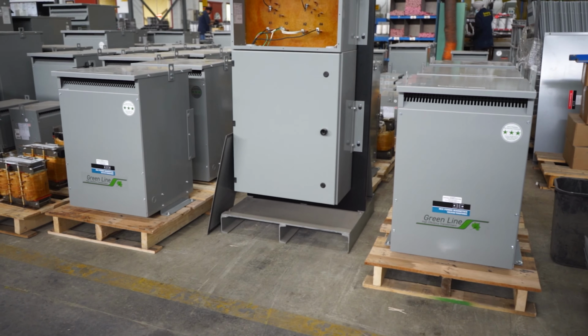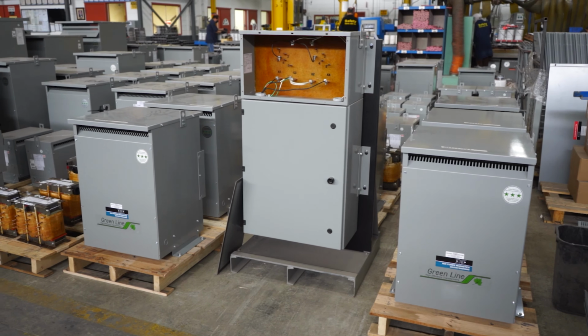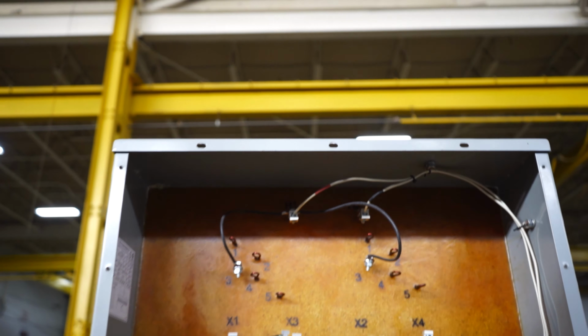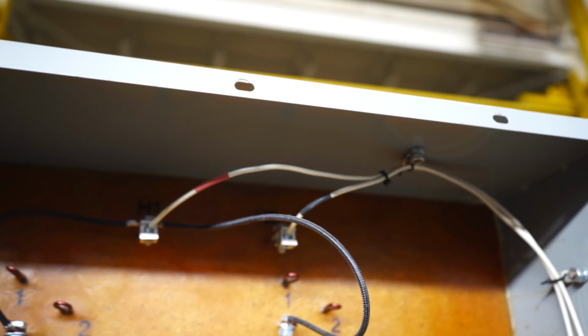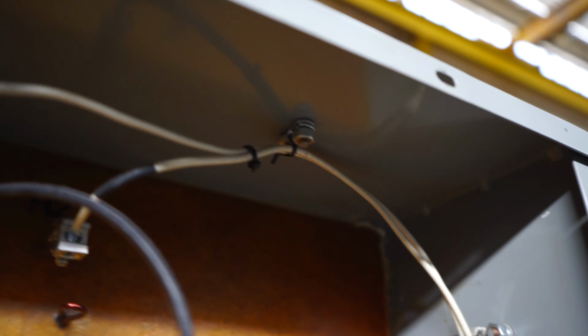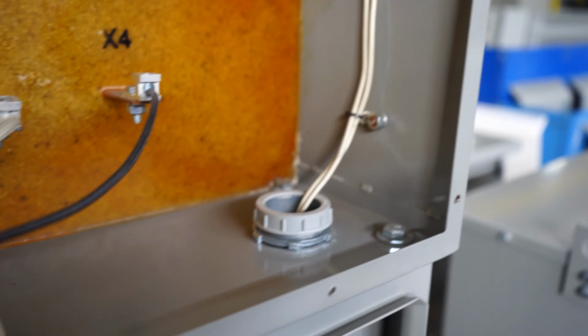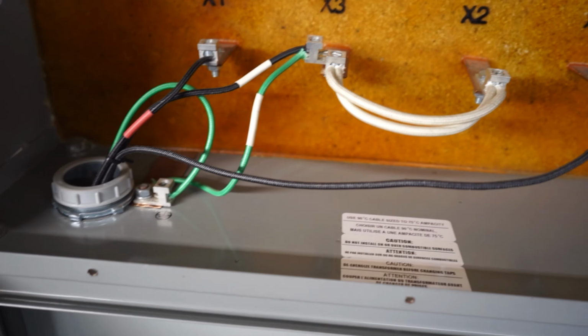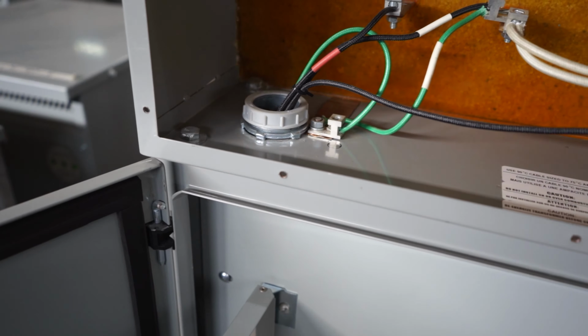The only time the transformer compartment should be accessed is for changing primary voltage taps or routine maintenance and inspection. Electrical approval for the site is simplified as the integration of primary, transformer, secondary, and branches are all done within a UL and CSA approved assembly.